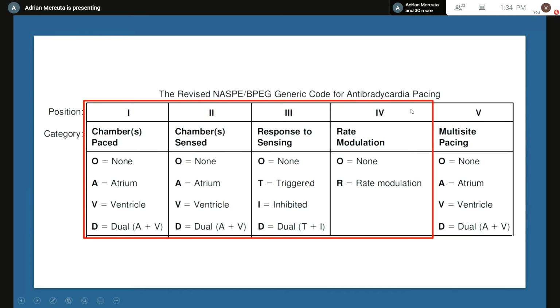That means sometimes you can associate the P wave, the atrial electrical activity, with stimulated ventricular activity, and when the sensor senses the P wave, it gives a stimulus to the right ventricle, and will do this association between the P wave and ventricular stimulation.